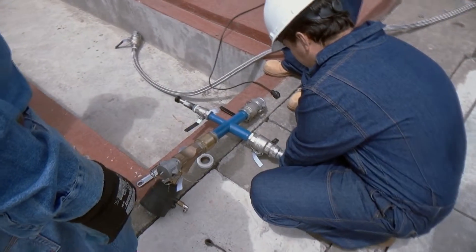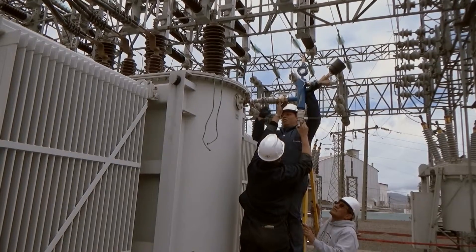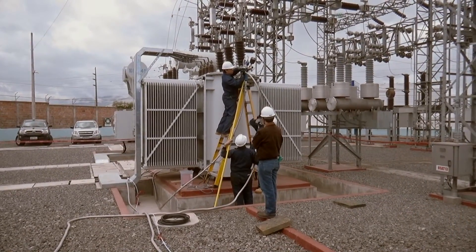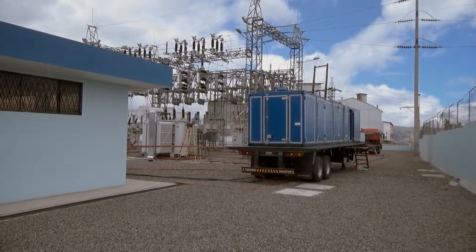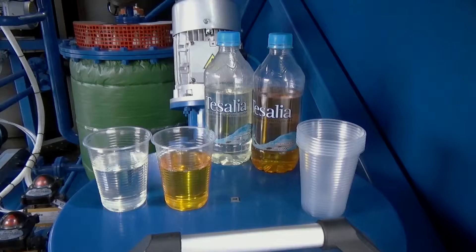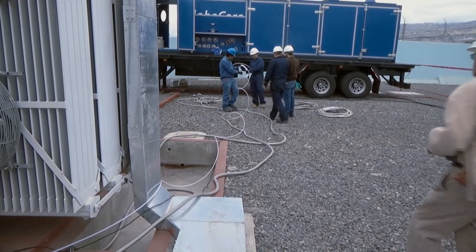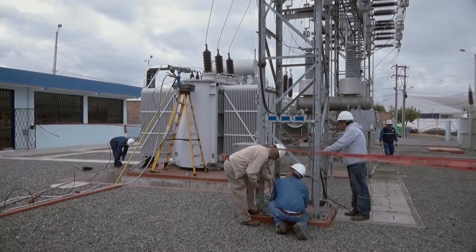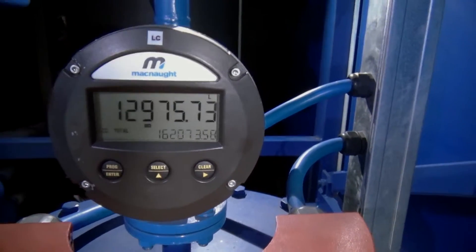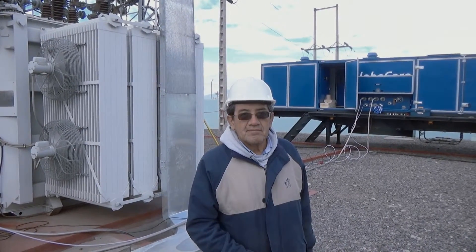This oil regeneration unit is the best in its class among the GlobeCore equipment and occupies a special niche in the company's production because of its high efficiency and capabilities. The functions of this unit are oil regeneration, thermal vacuum drying of oil, and evacuation of the transformer. The CMM-12R unit carries out oil processing in an online transformer without switching the transformer offline.